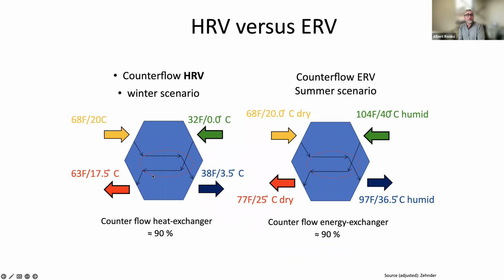In extreme cases, this is kind of what it looks like. Counterflow HRV is on the left side. Counterflow ERV or enthalpy recovery is on the right-hand side. And winter scenario where it's freezing outside, the green arrow, and it's 70 degrees, 68 degrees inside. Essentially, we're just going to transfer heat and no moisture is going to change hands at all because it's a plate heat exchanger. It's not designed to do that.